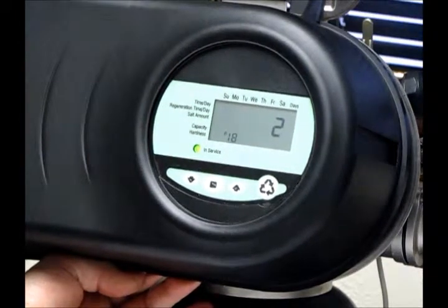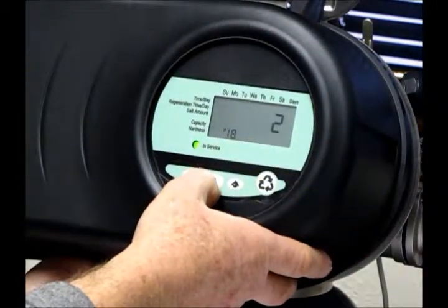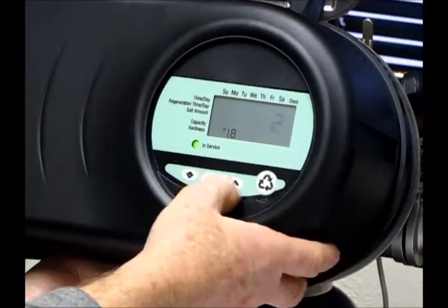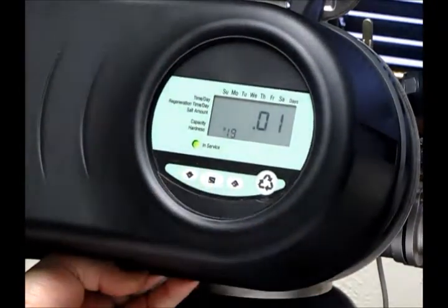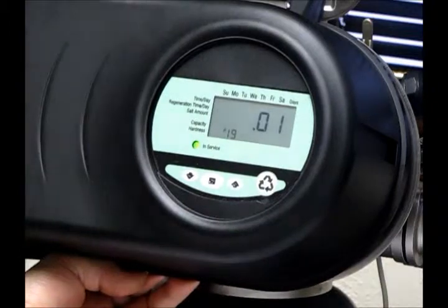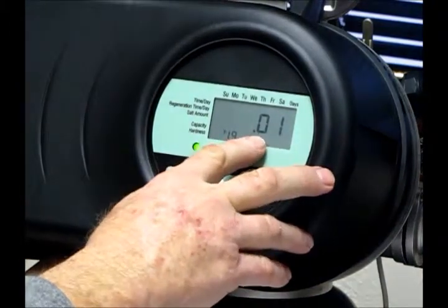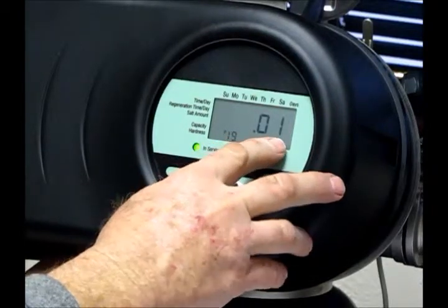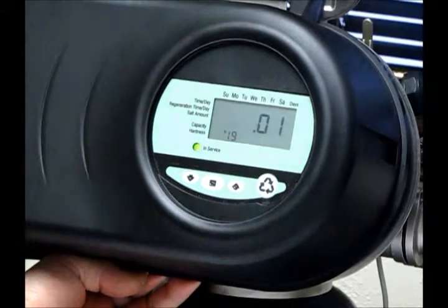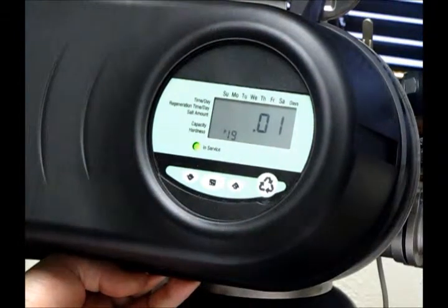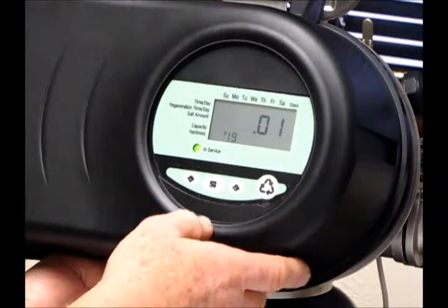We're using a Water King meter, and that tells us what meter we're using. It's a user defined meter. Change that to a 3 and set that. Okay, P19 is the K factor of the meter. You want to note on this screen it says 0.01. It's not 0.1 or 1.0, it's 0.01. The flow meter that we're using today is a 1.5" flow meter, which has a K factor of 28.